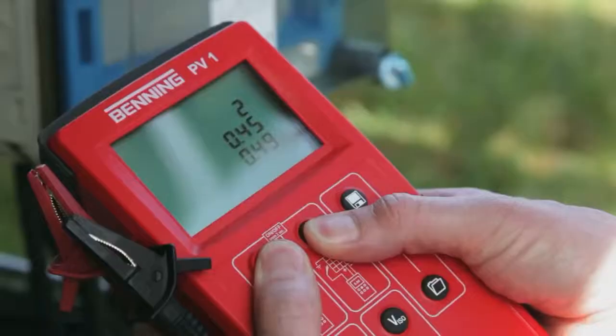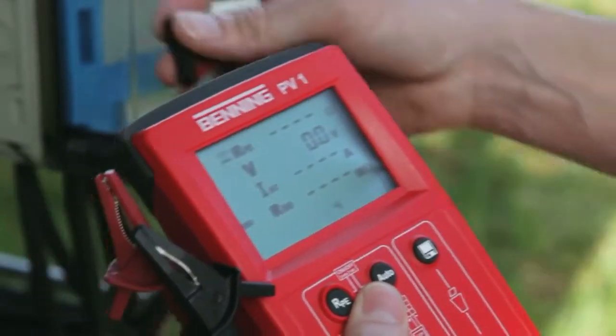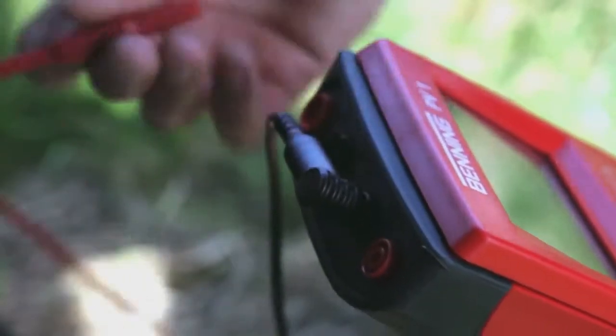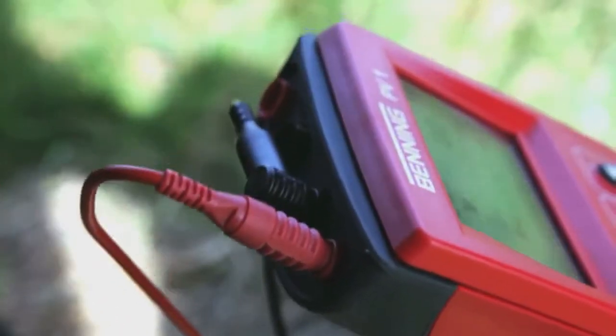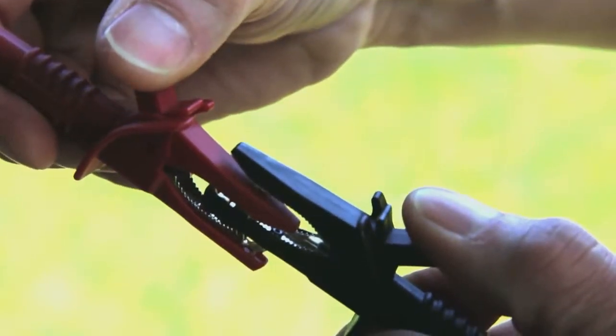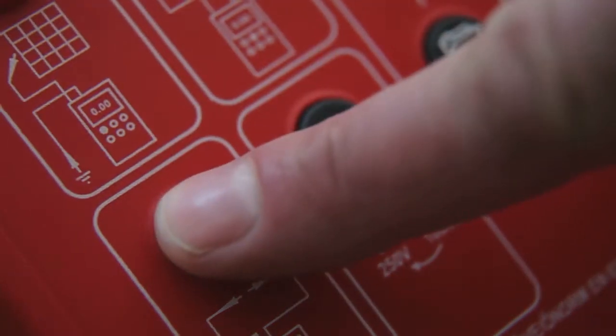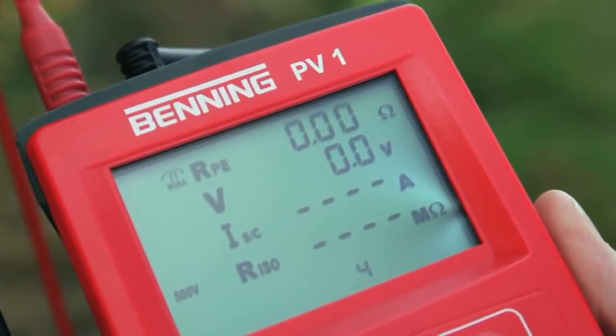After having switched the Benning PV1 on, and after having connected the measuring lines, first carry out a null balance in order to compensate the measuring line resistance. For this, press the null balance key and check the null balance on the display.